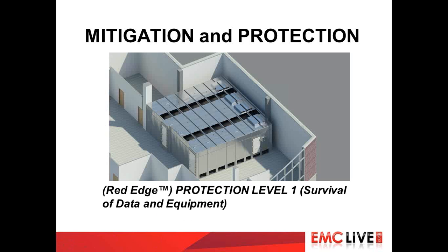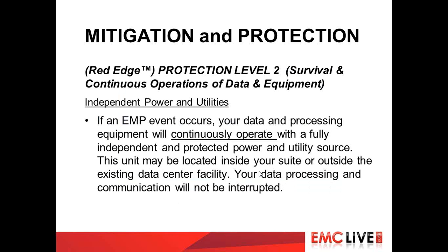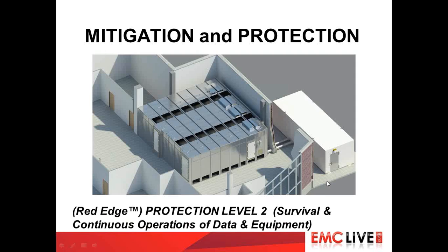And this is an example of a standalone shielded EMP enclosure that might be residing within a building. So it is standalone. It's reliant upon the parent facility for all of its utilities. What we look at secondly is what we call level 2, and that's survival and continuous operations of data and equipment. And in this scenario, if an EMP event does occur, the utilities will continue running. So the cooling systems are protected, the backup power is protected, the UPS systems, and any other support functions necessary to keep the data center running.